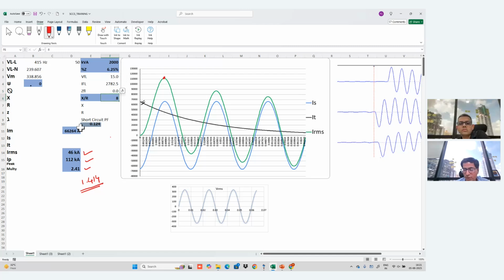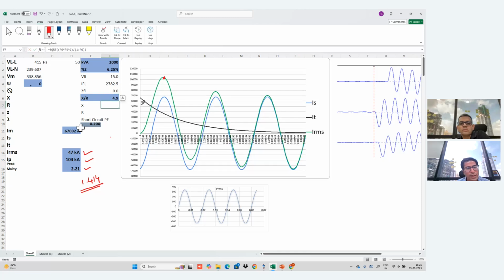Now suppose instead of 8, I have an X by R of, let's say, 4.9, which is the ideal case for a testing circuit by IEC, which will result in a power factor of 0.2. Now, if you see, the RMS has not changed. The total current is still 47, but the peak has reduced from 112 to 104. And the multiplying factor, you can see, is 2.21.